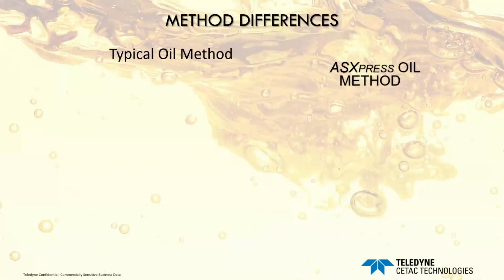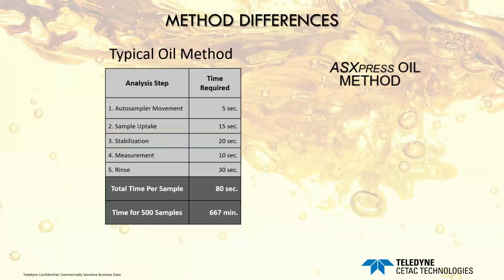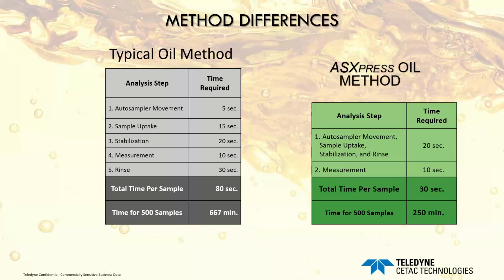All right, so here we have a time comparison between traditional sample aspiration and the ASXpress Plus. Using the traditional method, we come up with a time per sample of about 80 seconds. All right, using the ASXpress, we're able to go from 80 seconds per sample to 30 seconds per sample. So it's a savings of 50 seconds per sample. When you're running 500 samples a day, those 50 seconds can really add up. Here we've gone from over 11 hours to just over 4 hours.